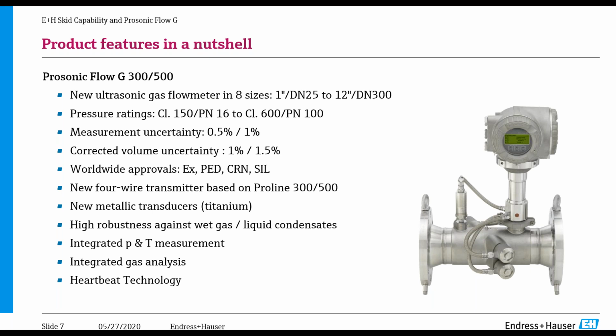If you do get the pressure and temperature, we have what we call an integrated gas analysis package. And this allows us 2 different features. One is compensating for pressure and temperature to get into standard cubic feet, so corrected volume. And the other one is a concentration measurement of methane, and I'll get into that. And we have Heartbeat Technology, which tells us the health of the device. So it's a diagnostics capability showing how healthy the meter is operating, seeing if there's anything wrong.